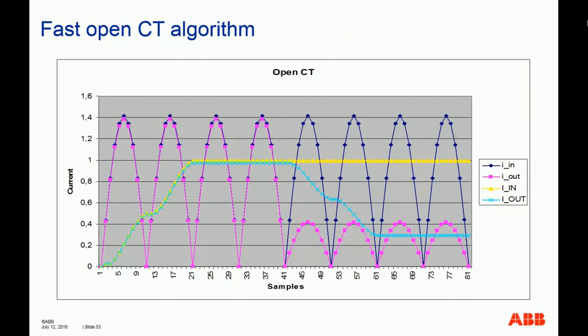In addition to that, what if the CT actually has an open circuit or short circuit? So basically, it doesn't pass the current to the relay anymore. So you can see how the relay analyzes this or prevents from operating incorrectly. So at the beginning, you will see that the currents coincide during normal load, but just after a certain time, the relay concludes there is a normal load situation, but all of a sudden you have a drop in the outgoing current. You can see here the incoming current stays the same because there's no fault, but there's a drop in the output current, so for no reason. So the relay will conclude that this is an open CT situation.